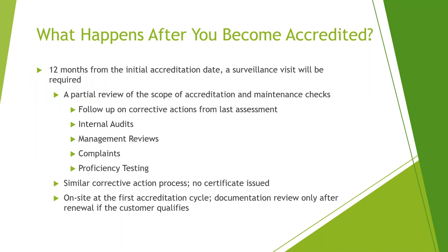Now for some FAQs on things we get a lot from clients before and after accreditation. What happens after you become accredited? We require a 12-month surveillance visit to check how you're doing — we'll look at past corrective actions, see how you've implemented those, and check the annual requirements in the standard. Surveillances are typically about a day depending on the size of your laboratory. There is a similar corrective action process, but we don't issue a new certificate as your certificate is still in good standing.